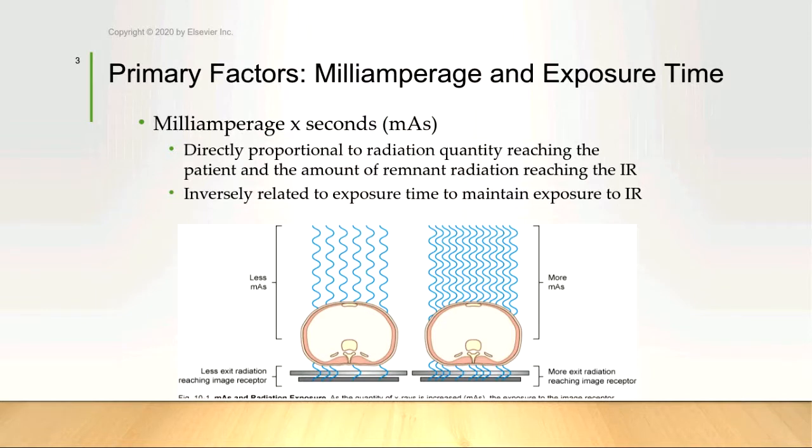And we select things like our milliamperage, our time, our kVp, and realistically, depending on what kind of control panel we have, we're either selecting separate milliamperage and exposure time, like in room 1, or you're just choosing a combined factor of your mAs overall, kind of like we have that capability in room 2, and a lot of our clinical sites, you're just simply selecting an overall mAs value and deciding if you want small or large focal spot.